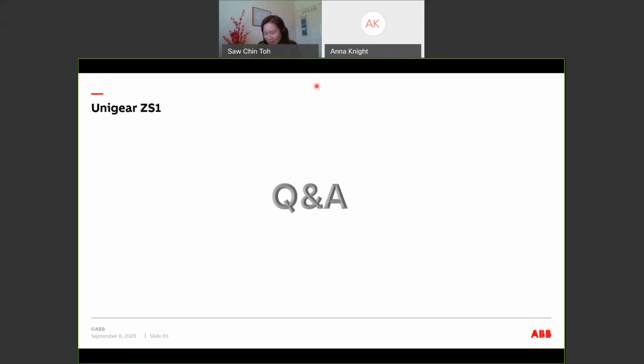Okay, thank you. Another one here is for outdoor switchgear forced ventilation. Do you have a guide to select or calculate the needed ventilation? We have cooling and heating requirements. The UniGear ZS1 is actually an indoor panel. So to put it in an outdoor application, we will either need to put it in an outdoor enclosure, or put it in a prefabricated room, depending on the size of the switchboard that you have on site. If it goes into a prefabricated switch room, normally you have air conditioning.